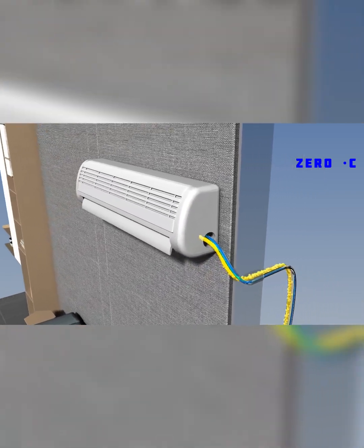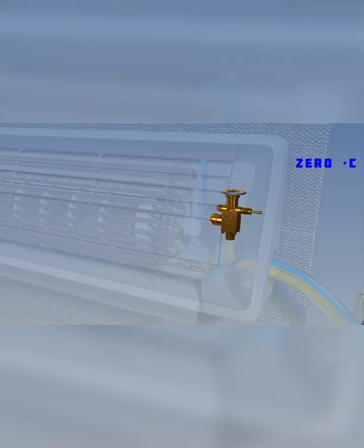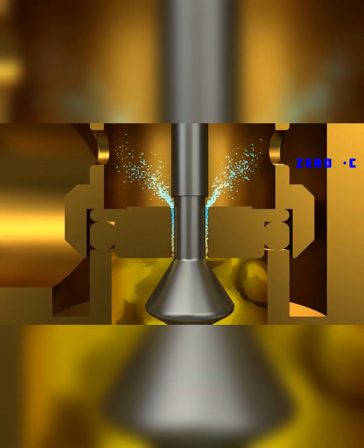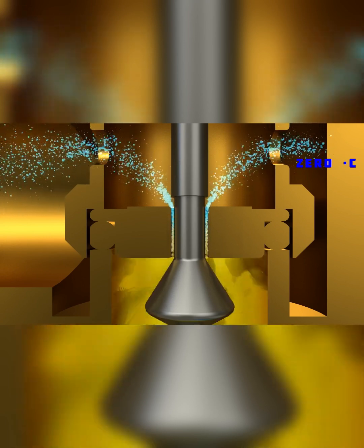Although the refrigerant has thrown off some of the heat as it passes through a condenser, it is still hot, with temperature at about 50 Celsius. The refrigerant in high temperature and high pressure liquid flows into the expansion valve. The refrigerant which used to flow in large space now passes through a narrow area and its pressure drops as it goes. When the pressure drops, temperature drops dramatically as well. The cool refrigerant is now sent to an evaporator.